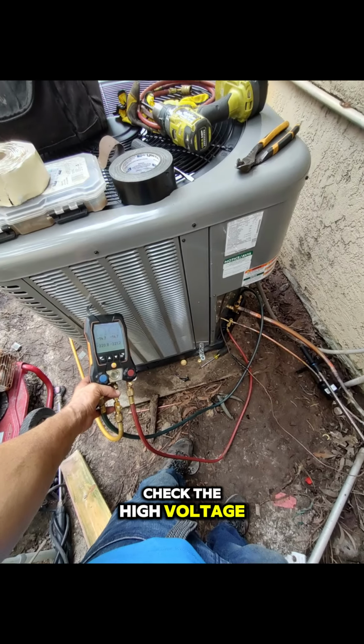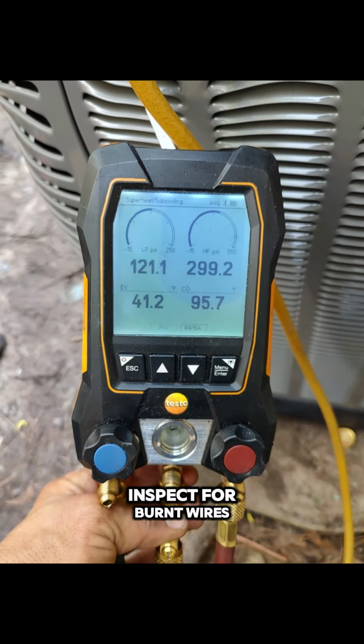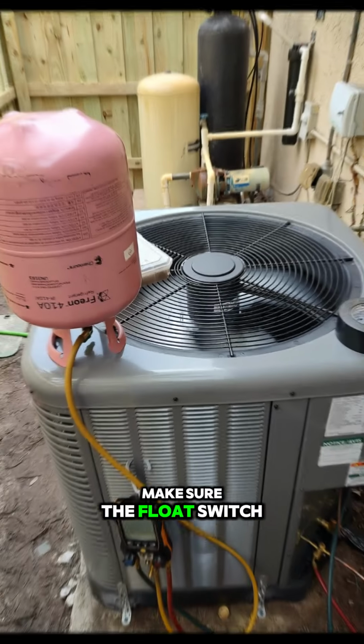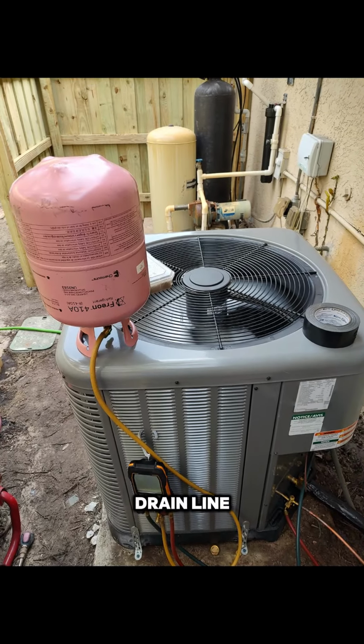Step 5. Buzzing but not starting. If the unit is buzzing but not starting, check the high voltage fuse at the disconnect or breaker panel. Inspect for burnt wires. Make sure the float switch hasn't tripped, usually from a clogged drain line.